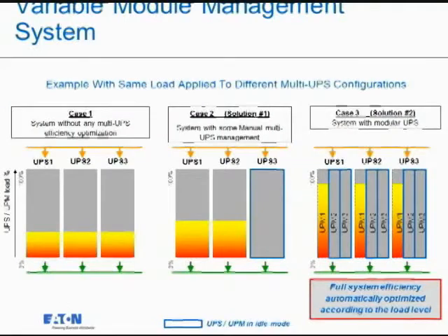But our estimates show that simply by doing that, by increasing the loads now to roughly 40% on each module, or 30% on each module, we're probably going to see about $250,000 savings over 10 years. Simply by manually going in there and doing that exercise to optimize the systems.